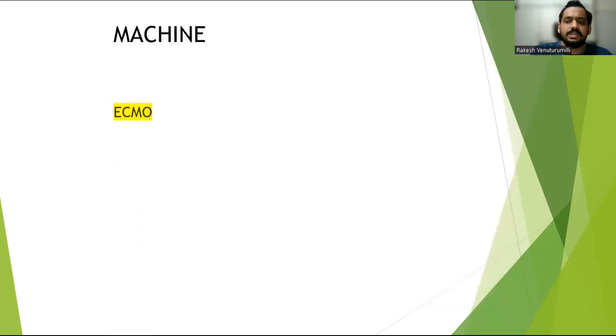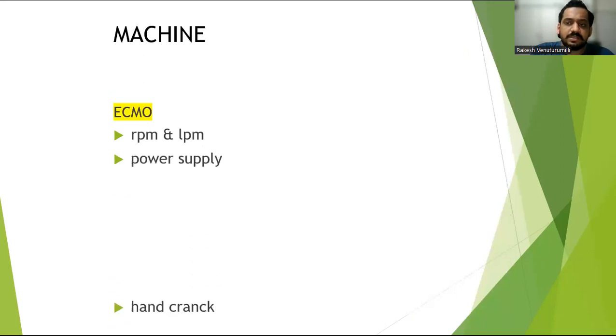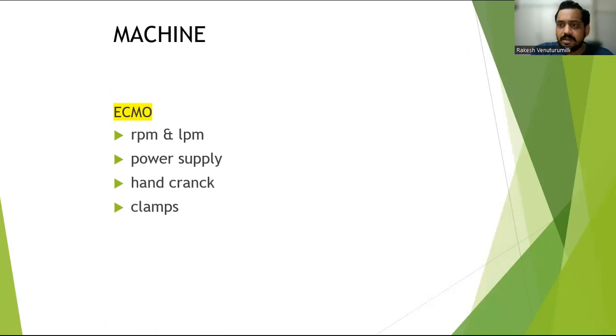So coming to monitoring of the machine. What are the things you need to monitor on the ECMO machine? You need to have documentation of your RPM and LPM, revolutions per minute and liters per minute. You need to see that the power supply is always connected to the UPS part of your power plug, and then the hand crank should always be positioned in parallel to your original pump, so that changing of the pump should be easy for you. The hand crank should not be somewhere else where you cannot do the things within time.